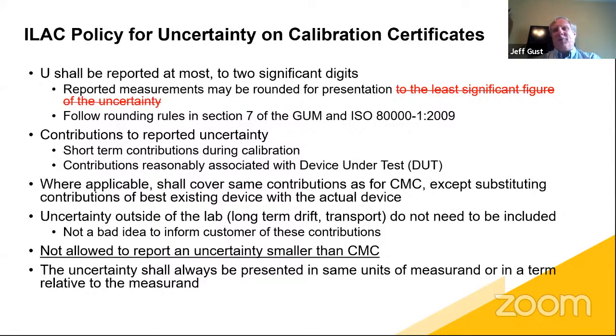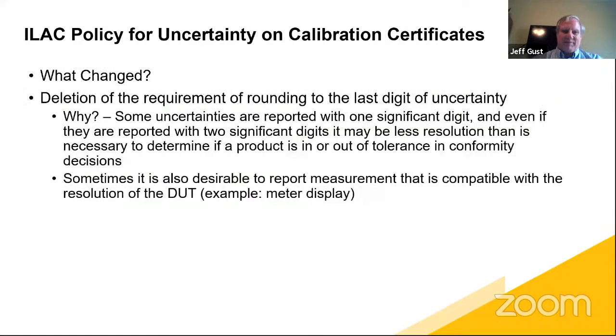We look at these on our primary standard things like resistors. Has there been a shift due to travel? And we have to account for that uncertainty if that actually realizes itself, in addition to what the NMI uncertainty was. And again, this is where it's very clearly stated, you are not allowed to report an uncertainty on your calibration certificate that's smaller than what you have on your scope. That's a violation. And of course, the uncertainty shall always be presented in the same units of the measurand or in terms relative to the measurand as well.